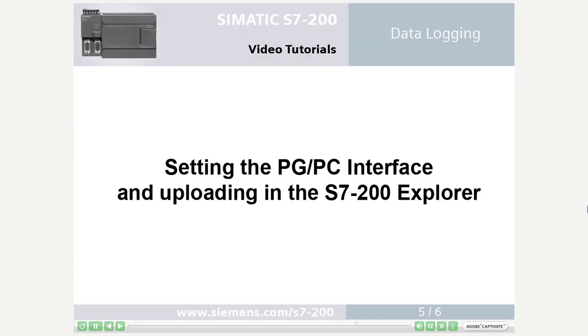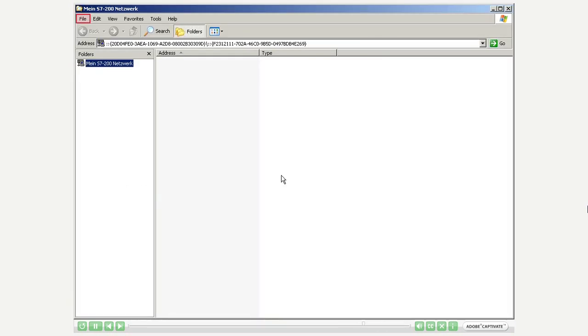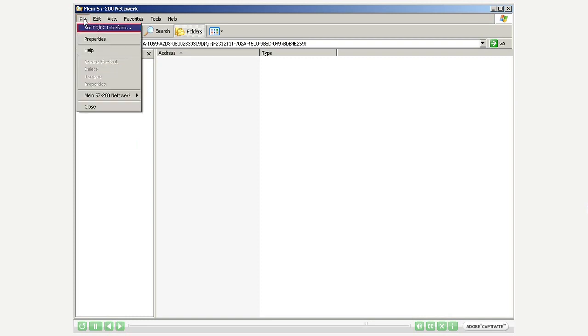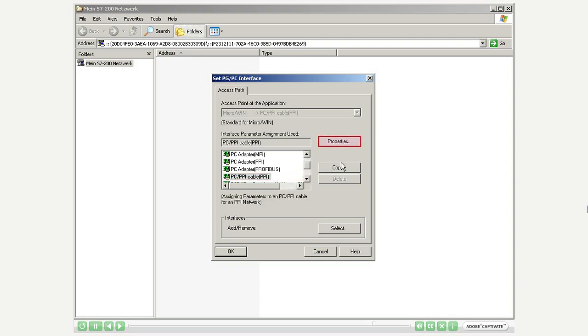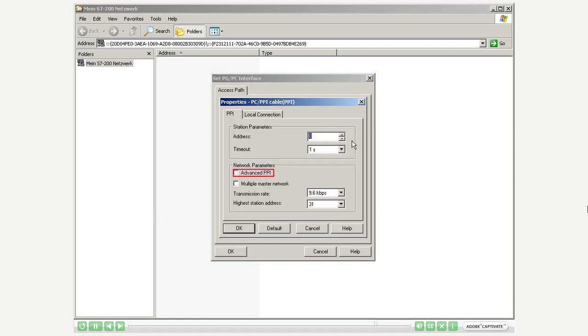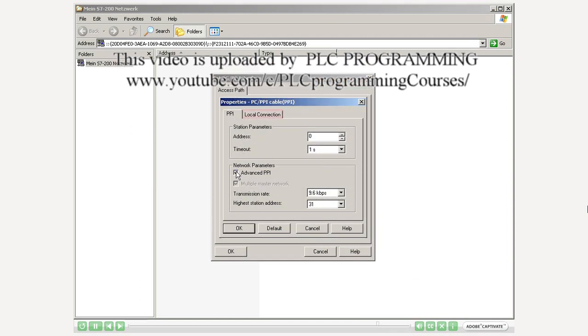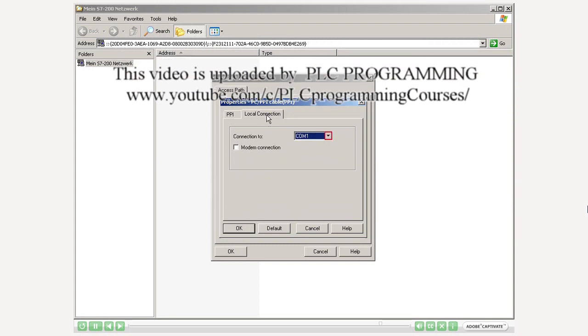Step 5: Setting the PG/PC interface and uploading in the S7-200 Explorer. Call up the PG/PC interface settings in the S7-200 Explorer. Select the PC/PPI cable. Activate Advanced PPI. Go to local connection. Select USB.